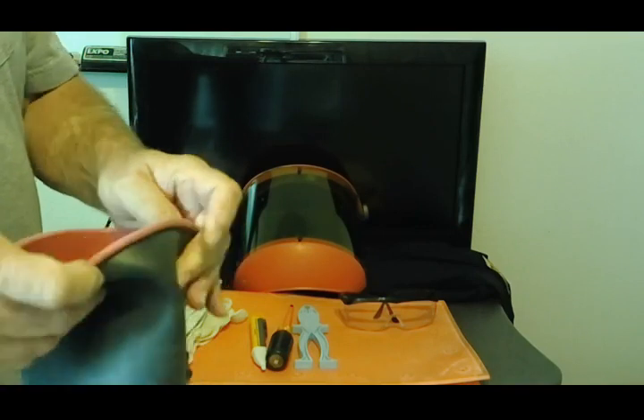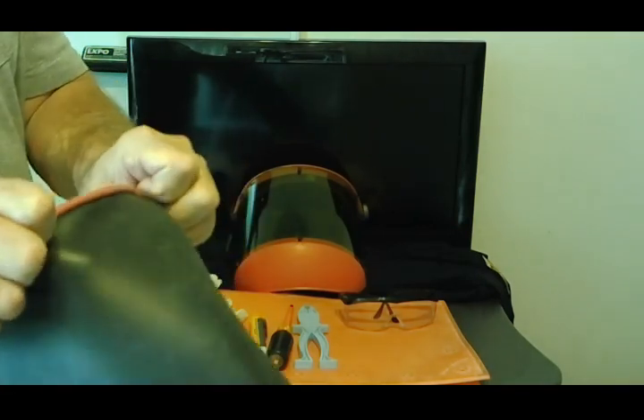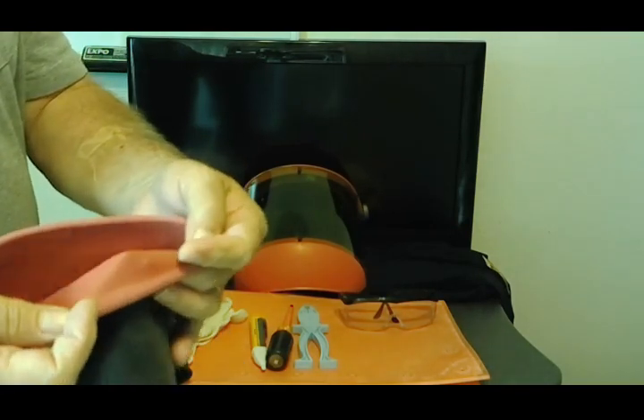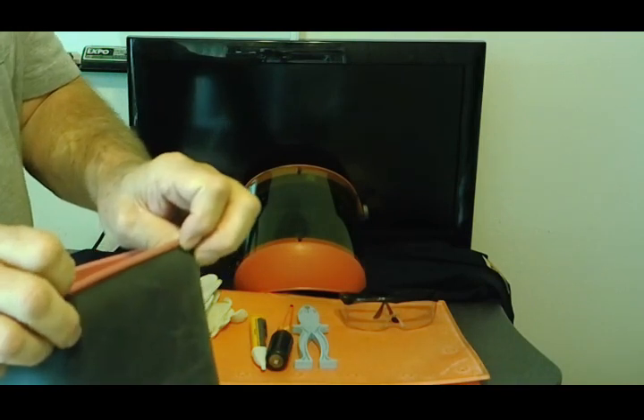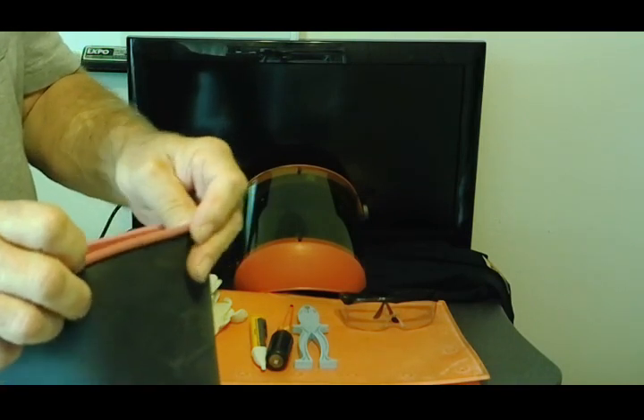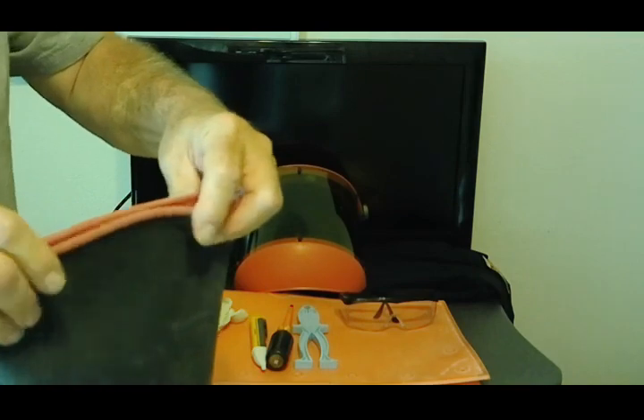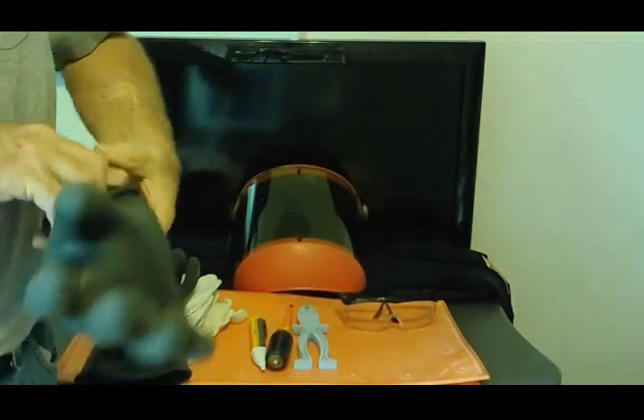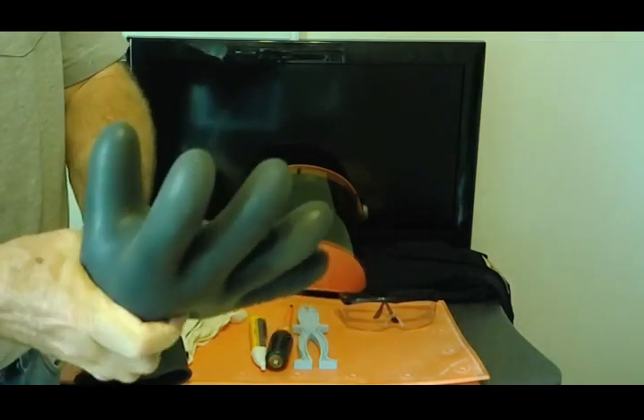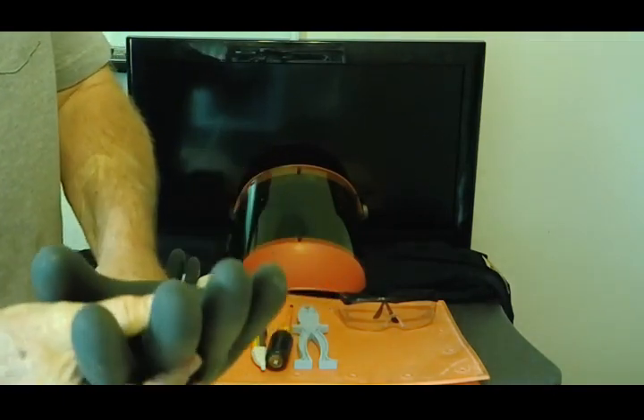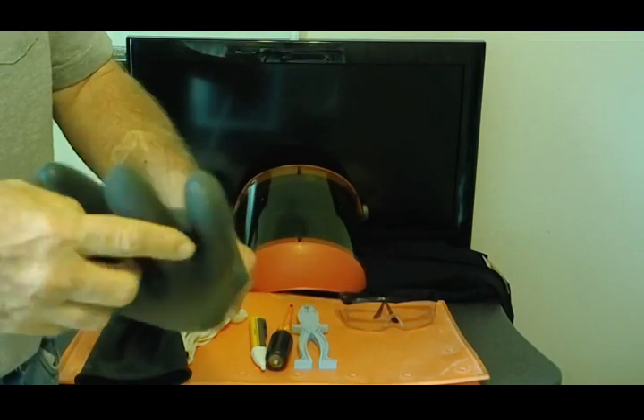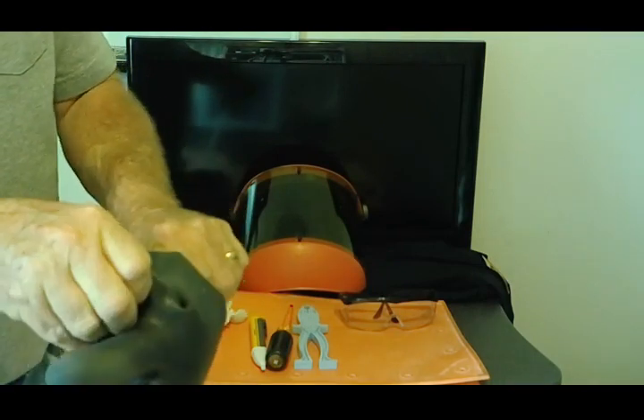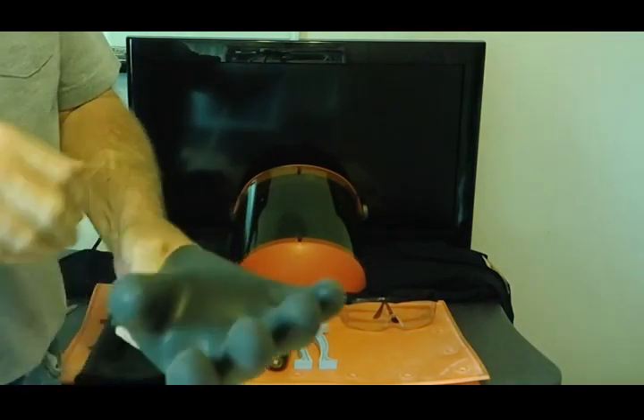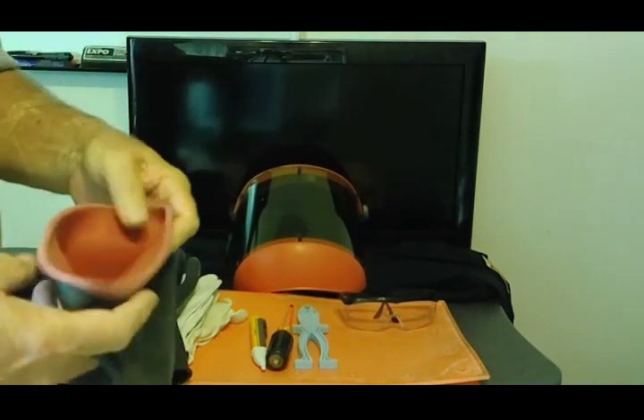Now, some of the gloves are going to have two colors, one on the outside, one on the inside. Again, they could be any colors. The reason for that is it makes it simpler and easier to test them. So once I capture air in the glove to test it, if there's any damage, it's going to show one color through the other. So you'll be able to see it much easier. That's the purpose of the two colors.